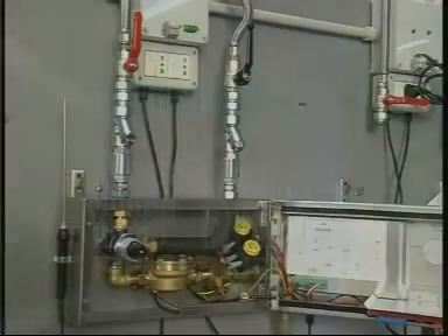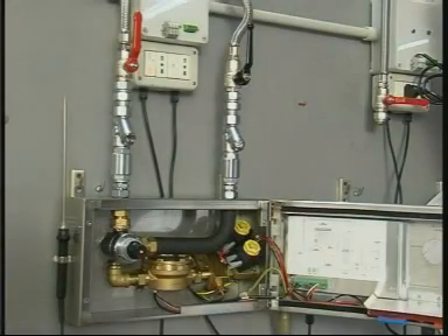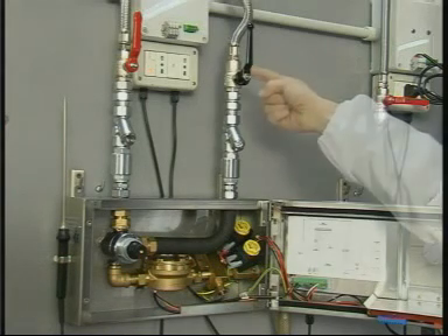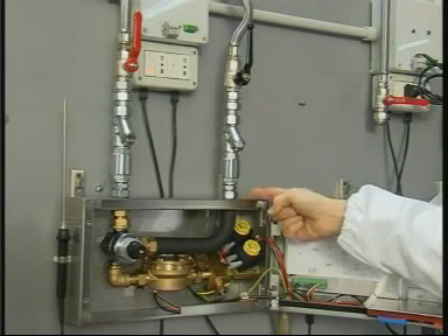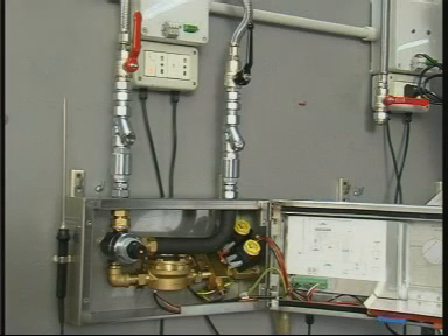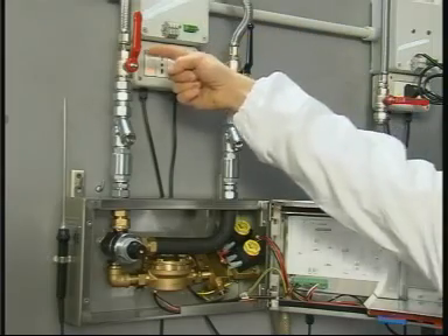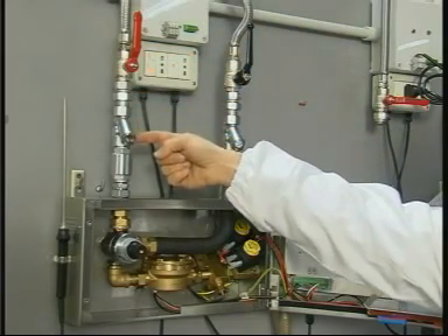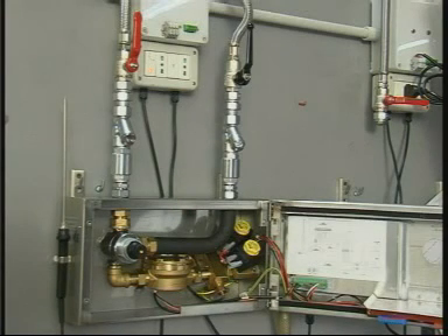Solution: control inlets. The first thing to check is the temperatures of the inlet waters. That is to say that at the inlet of the colder water, the temperature of the water coming from the chiller or from the city network is lower than the requested value, and that at the inlet of the warmer water, the temperature of the water coming from the boiler or from the city network is higher than the requested value, maximum 60 degrees centigrade or 140 degrees Fahrenheit.